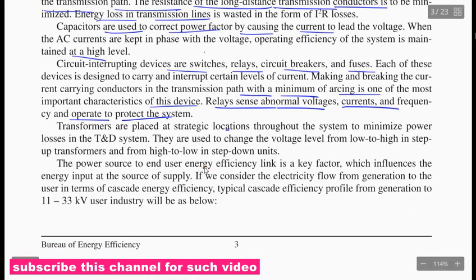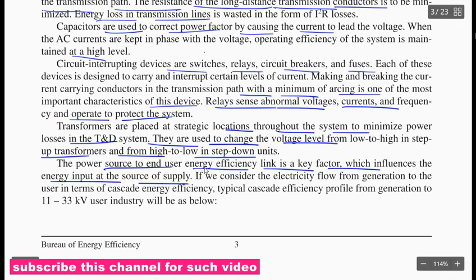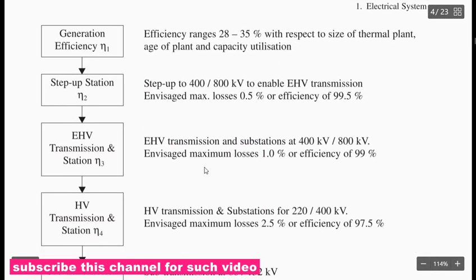Transformers are placed at strategic locations throughout the system to minimize the power losses in the T&D system, and they are used to change the voltage level from low to high, step up transformers, and from high to low, step down units. The power source to end user energy efficiency link is a very key factor which influences the energy input at the source of supply. If we consider the electricity flow from generation to user in terms of cascade energy efficiency, the typical cascade efficiency profile from generation to an 11 to 33 kV industry user is given below. Generation efficiency range is 28 to 35% with respect to the size of the thermal power plant, age of the plant and capacity utilization.